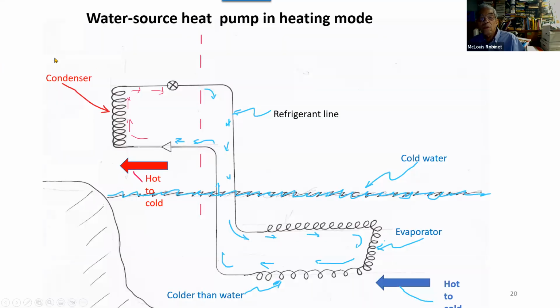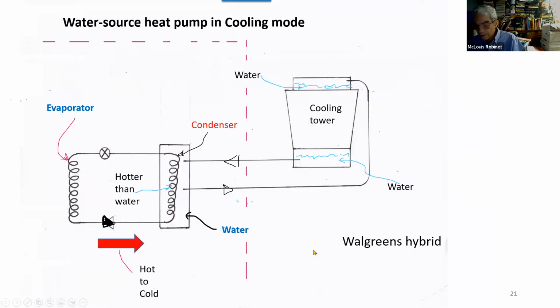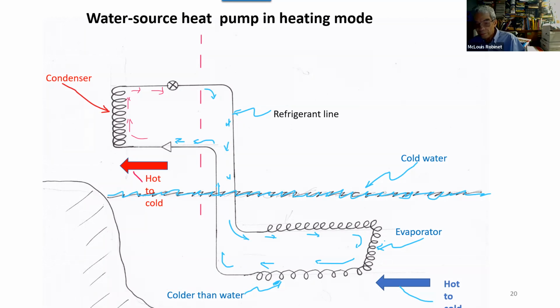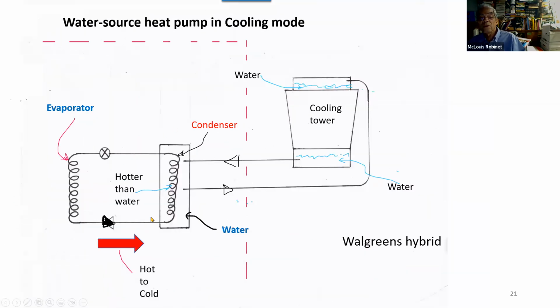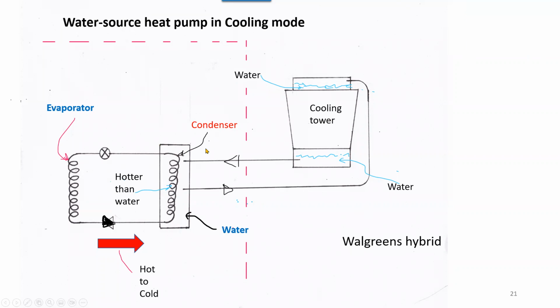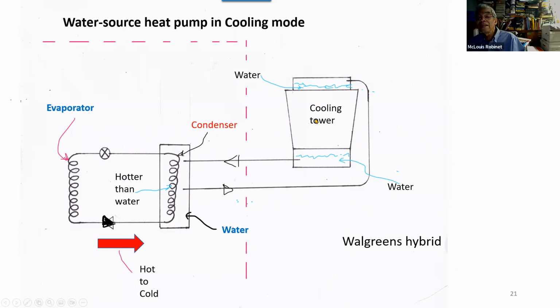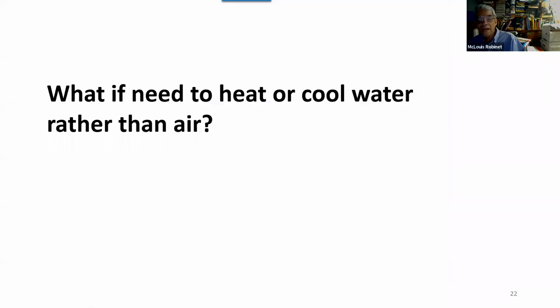So, at a water source heat pump, you would take the evaporator and put it in the water. That's actually done. Instead of doing that, you could use a cooling tower to have a water source heat pump. Actually, the Walgreens on Madison and Oak Park Avenue has a hybrid system. They have a geothermal system and a cooling tower. So it's a hybrid.